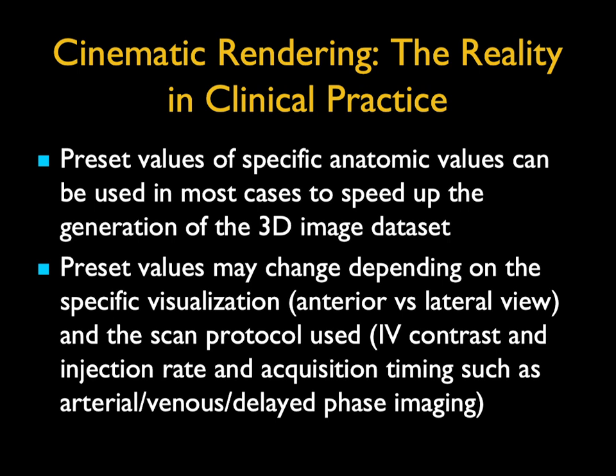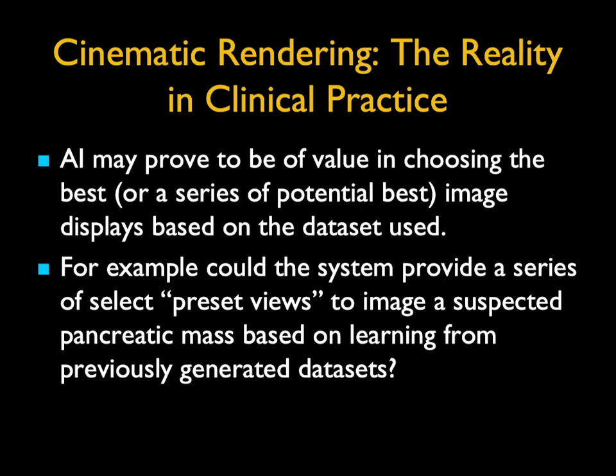The reality: preset values can be used in most cases to speed up the process and make it easier. Preset values may change depending on the specific visualization and the scan protocol used. You need to do the same scan protocols every time — if things are too early or too late, you're going to need to change the parameters. Consistency is important. AI may prove to be of value, and we're looking at AI as a way of choosing the best parameter set.